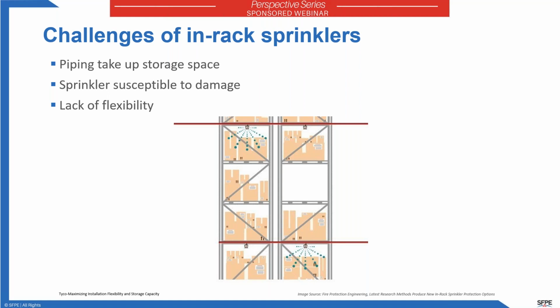Obviously, they'd be much closer to the fire source than ceiling-only protection, so the fire will be much smaller when the in-rack sprinkler operates. And typically, the hydraulic requirements are less since the sprinkler is closer and the fire is smaller. You're able to address a fire in the rack with less water than ceiling-only protection.